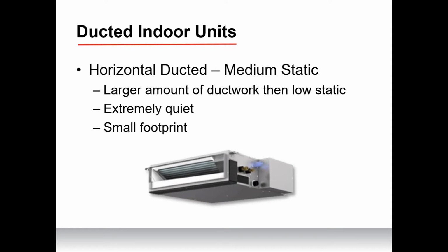Next is a medium static horizontal ducted indoor unit. This air handler has a higher external static pressure and higher CFM, which enables much more ductwork to be attached than in the low static unit. This unit's also very quiet, still maintains a small footprint. It's slightly larger than the low static unit, but it still maintains that horizontal footprint. So this is great for ducting whole floors, apartments, small homes. You can get a lot more done, a lot more ductwork on this medium static unit.